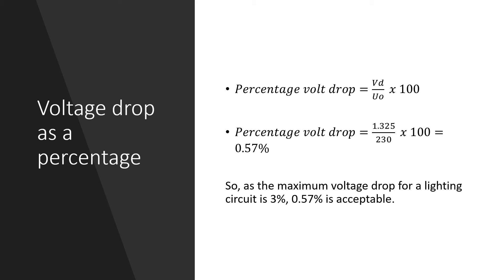So if the actual volt drop is 1.325 volts, we can convert this to a percentage by dividing by the voltage and then multiplying by 100. So if we take 1.325 and divide by 230 and then multiply by 100, that gives us a percentage of 0.57. So as the maximum voltage drop for a lighting circuit is 3%, 0.57% is acceptable.